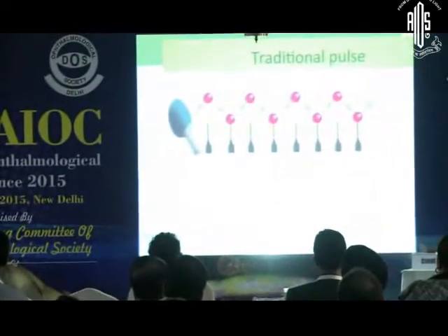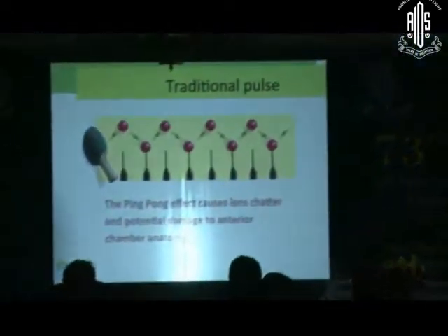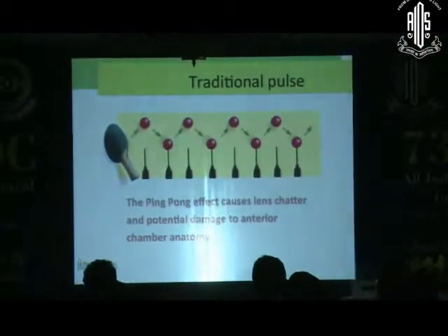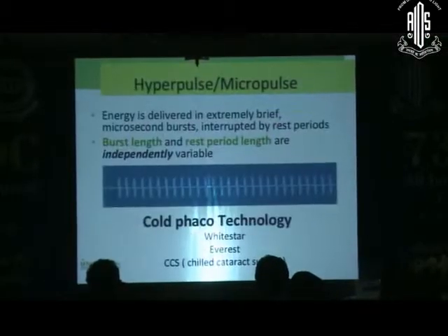The disadvantage with this traditional pulse effect is that there is a ping-pong effect which causes a lens chatter. That means each time the power is on, it can also push away the lens particles, causing chatter, and there is potential damage to the anterior chamber anatomy.